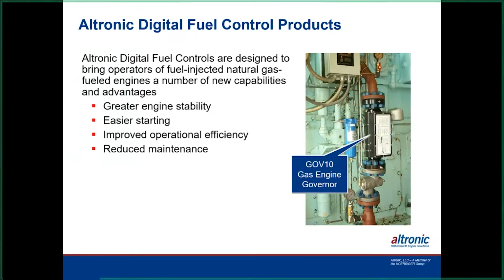Well, the first one we're going to go through, we're going to talk a majority on the GOV10, because it's a little more complicated than the AGV5 is. These are digital controls that are designed to operate a fuel-injected natural gas engine with new capabilities and advancements. It stabilizes the engine over the old mechanical linkages and the old hydraulic governors. It's a great improvement if you haven't had a chance to operate one on one of these large old slow speeds, or on some of the Superiors. It works there great also. So that improves the efficiency, and it eliminates a lot of the mechanical maintenance that you would have had in the past.